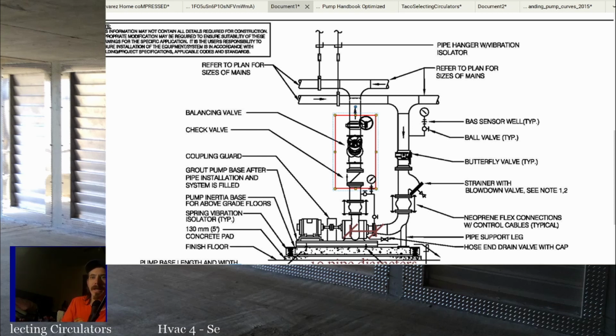But I think that's kind of the purpose of making sure you look at your net positive suction head before you start up a pump, is to make sure that you don't create a negative pressure on the suction side, because you not only run the risk of something like your pump seals leaking, because those things are finicky as they are. They're already finicky as shit. So you're dealing with a finicky part of the pump and putting it in an adverse condition. But not only are you doing that, but you're risking cavitation, right? You're gonna start cavitating inside the pump, and you're gonna damage the impeller before it has time to even start a whole life.